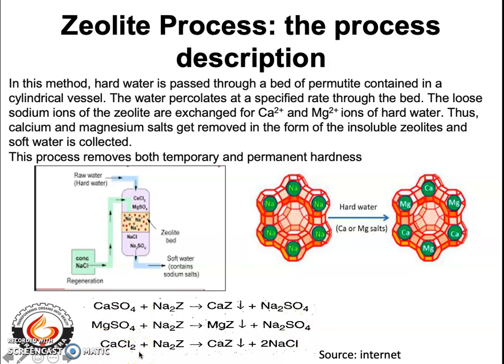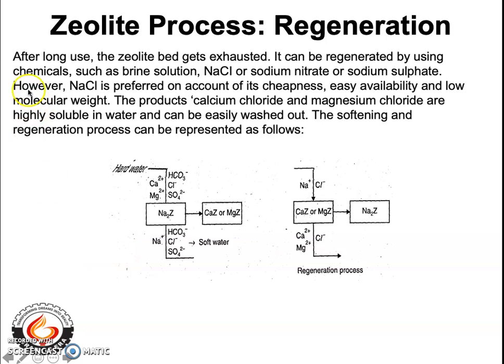After long use, the zeolite bed gets exhausted. It can be regenerated using brine solution — concentrated sodium chloride — or other chemicals like sodium nitrate or sodium sulfate. Sodium chloride is preferred on account of its cheapness, easy availability, and low molecular weight.